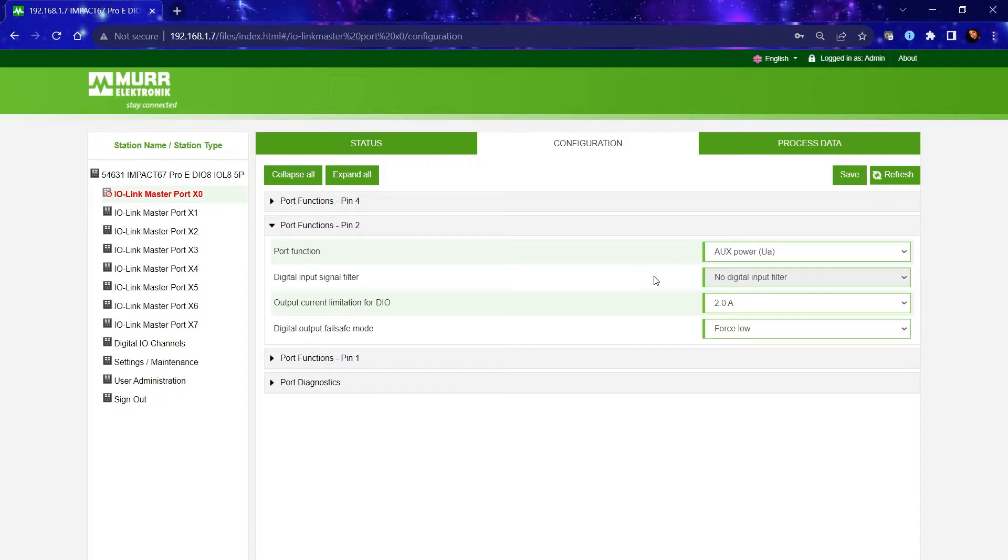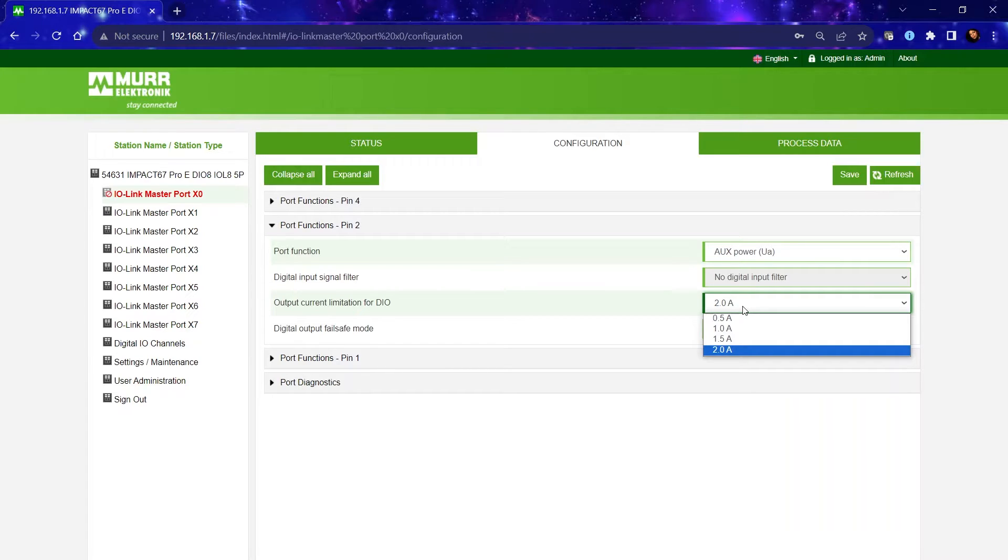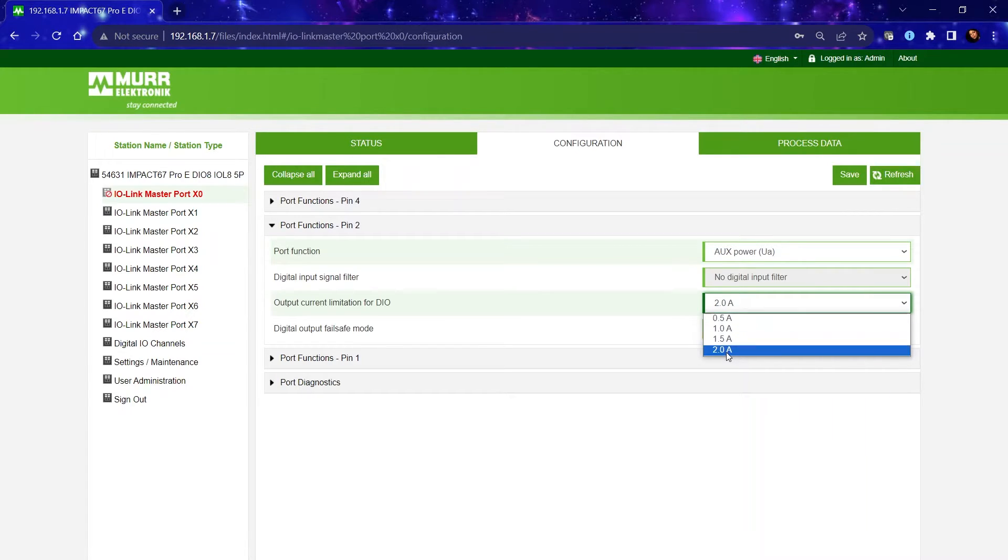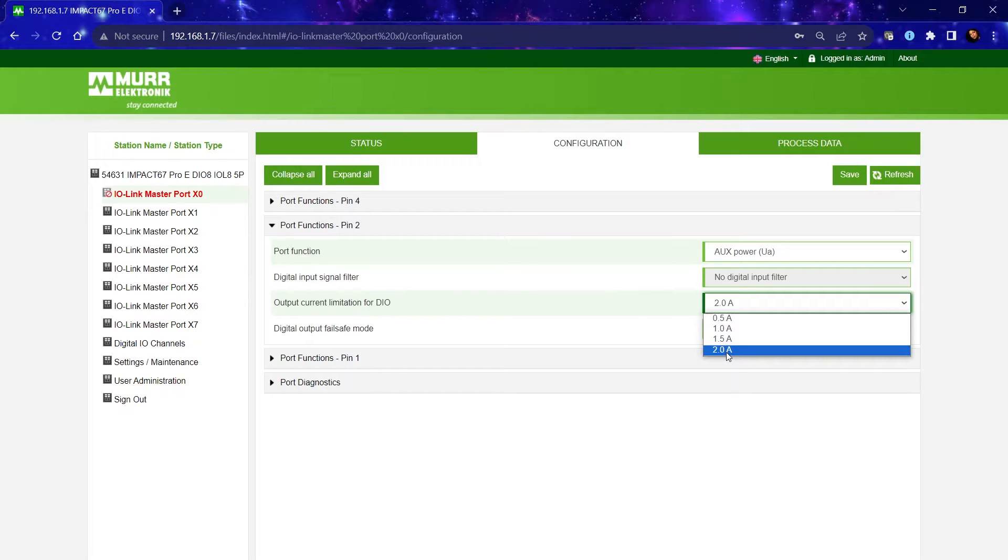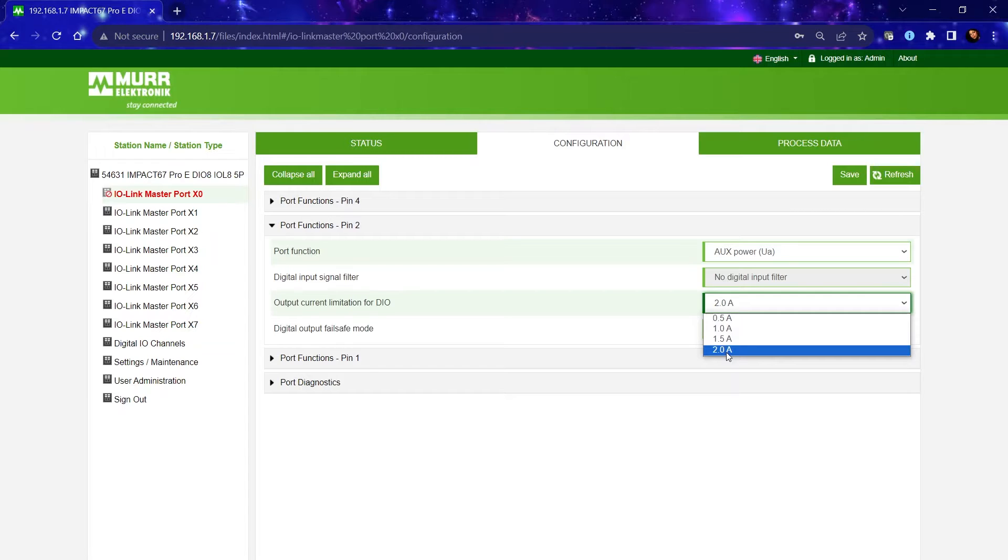Not only can you change the pin's function, you can also select the output current per channel between the range of half an amp to 2 amps. This comes in handy when connecting IO with various current settings. You want to select the current output on the block correctly so it can detect a diagnostic short in less time when it's set properly.